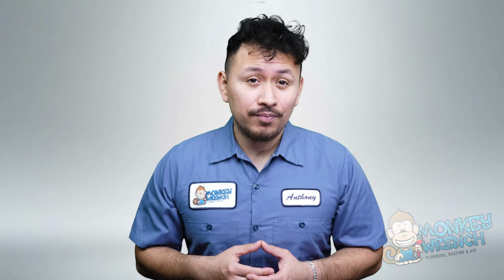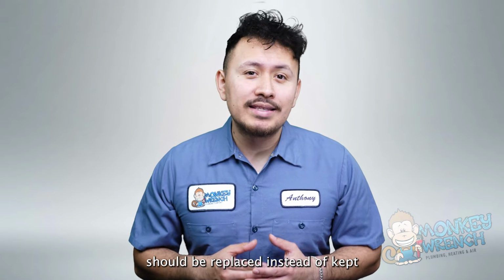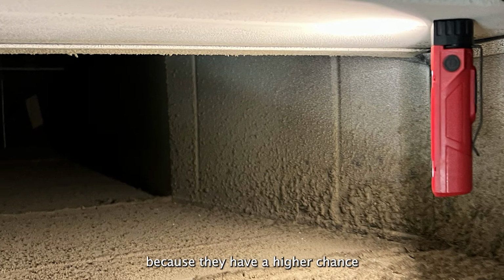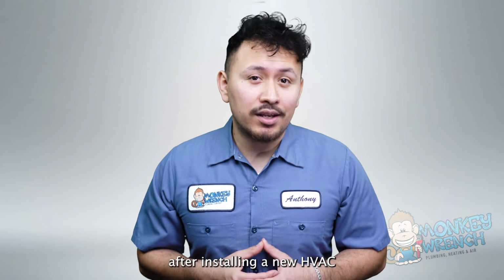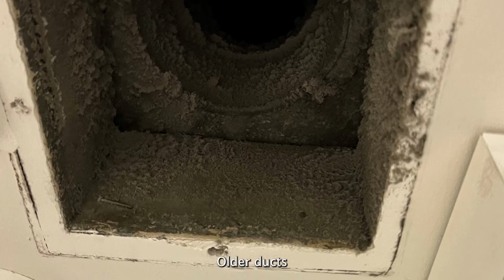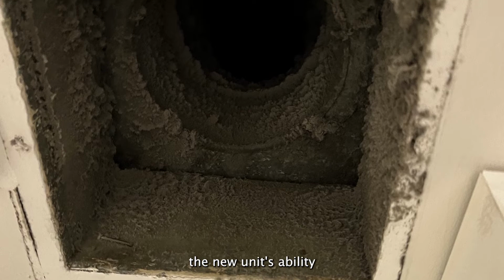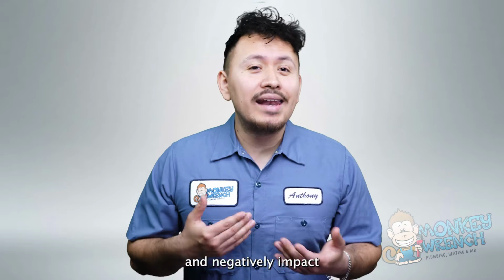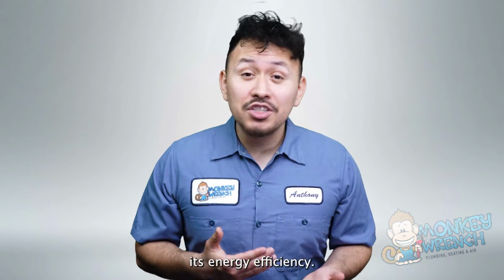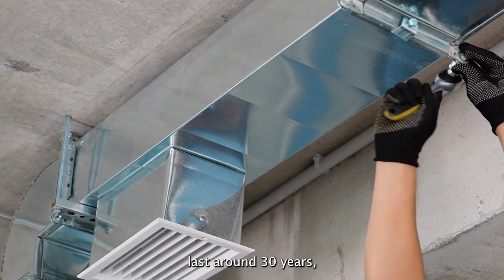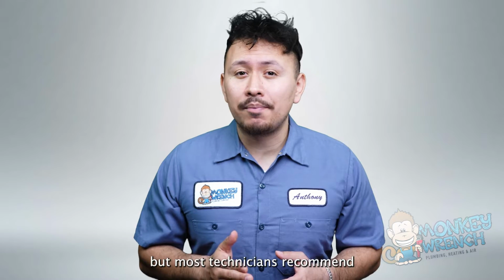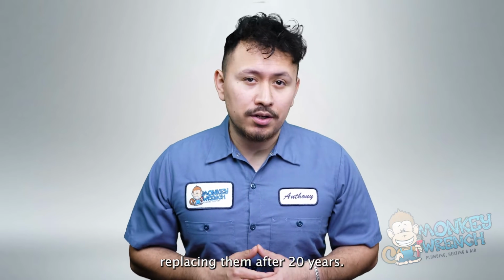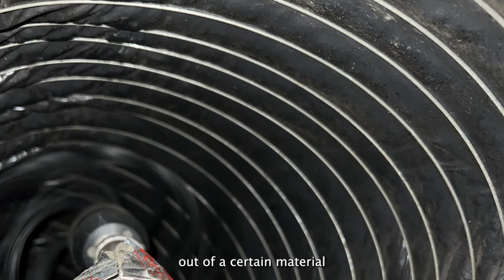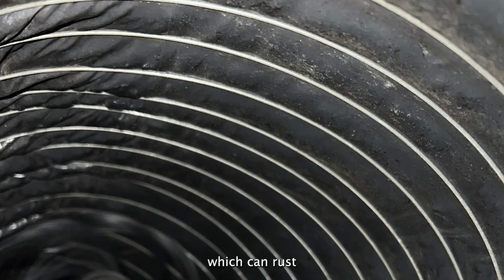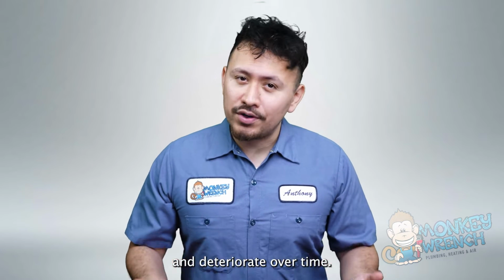Ductwork is old. Outdated ductwork should be replaced instead of kept because they have a higher chance of breaking down after installing a new HVAC system. Older ducts can also obstruct the new unit's ability to heat or cool and negatively impact its energy efficiency. Ducts can normally last around 30 years, but most technicians recommend replacing them after 20 years. Ductwork is made out of certain materials such as fiberglass and metal, which can rust and deteriorate over time.